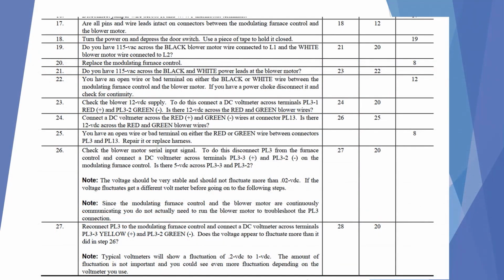In order to troubleshoot fault code 41, we're going to continue through the manual. One of the calls that we get quite often, because these are ECM motors, is the technician will tell us that the ECM motor has 115 volts or 230 volts to it, and it's not running, and they don't understand what's going on. In the troubleshooting guide, yes, it does ask you if you have the line voltage to the blower motor, which is an ECM motor, but that does not mean that the motor is going to run. The line power is to power the electronics in the back end of the motor. So in order to make the motor run, you need to have DC voltage commanding the motor to run and commanding the motor to stop. This is where these troubleshooting guides come in handy, because you need to know which wires to check and what voltage you should see.